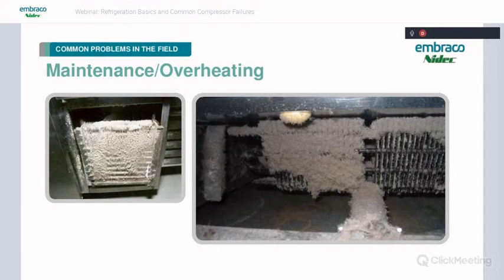It's going to heat up the oil. It's going to get the oil so hot, and the compressor is going to be so hot, it's going to cook the oil inside the bearings, and you're going to get all kinds of debris, and the oil is going to get cooked on the bearings and everything. It's going to cause all kinds of problems. Your valves aren't going to seal good anymore, and then it's all downhill from there.